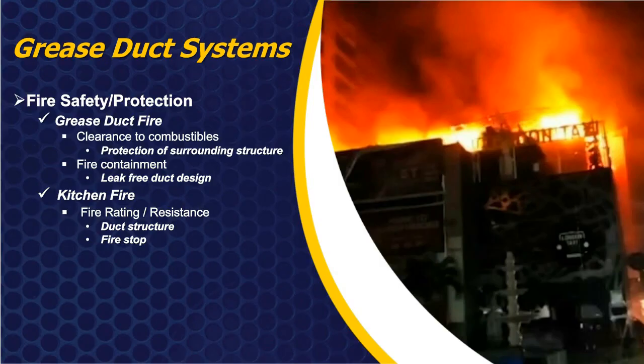When it comes to grease duct systems, there are 2 parts of fire safety and protection to deal with. And that's what we're going to deal with here: how ducts are constructed to make sure they're fire safe and code compliant. The 2 safety factors when it comes to grease duct are, first, grease duct fire. Grease vapors get into the hood or into the duct system, and they may collect. If a fire starts from grease inside the ductwork, we have to make sure that the duct system has proper clearance to combustibles so the fire inside the ductwork doesn't set the surrounding structure on fire. Second is containment of that fire inside the duct. Obviously, we don't want a fire inside the ductwork, but if that occurs, the goal is to contain it inside the ductwork, either suppress it with fire suppression equipment or have it burn on its own and not burn the rest of the building down.